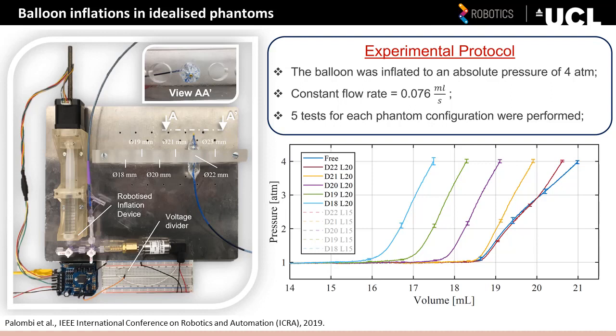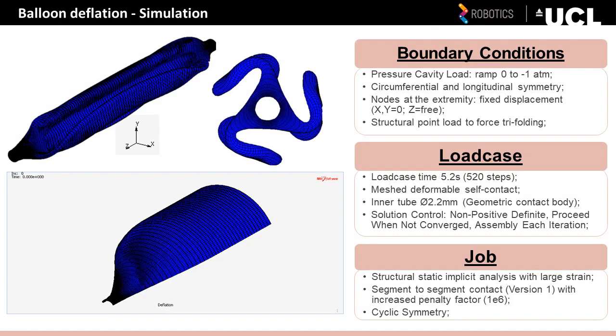The dashed lines represent averaged pressure-volume curves obtained for a different annular length — 15 mm in this case. From the experimental data, we can observe that if the diameter of the phantom is smaller than the diameter at which the balloon would start stretching if freely inflated, the position of the departure point depends significantly on the annular length. Therefore, it is impossible to obtain a direct unbiased estimate of the annular diameter from simple considerations on pressure-volume data alone.